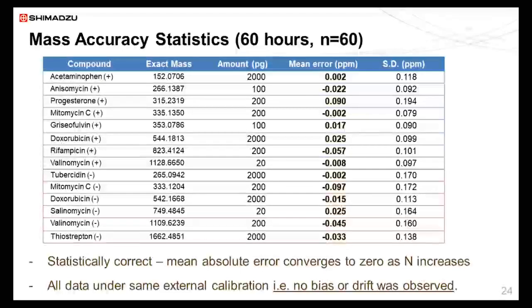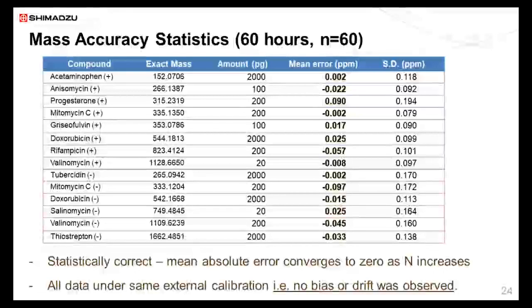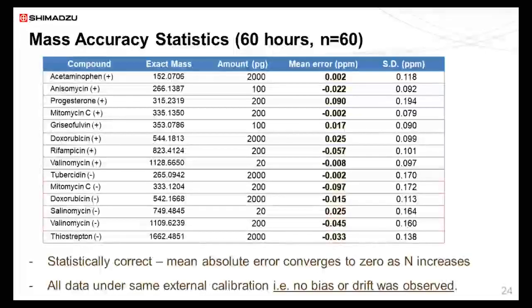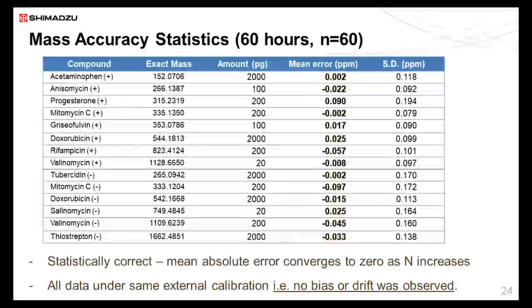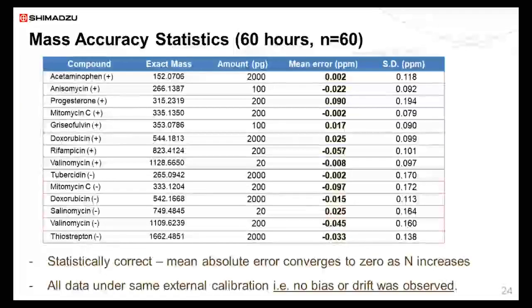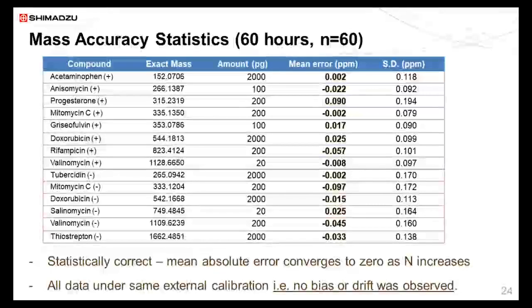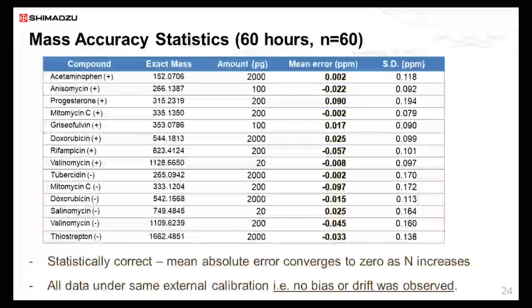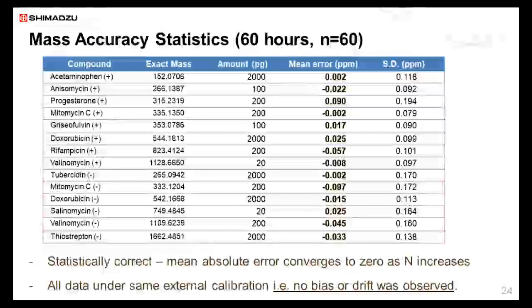And this is a statistically correct phenomenon because we've shown before that mass measurement accuracy is K over R root N. So if N increases, then it follows that the error decreases. And we've done this for 60 hours. We've done 60 measurements, so we're sampling quite a large number of ions. So we're expecting to see that the mean absolute error converges to zero. So this also shows that we're experiencing no mass drift or any systematic error that is causing bias. So all data under the same external calibration, no bias or drift was observed.